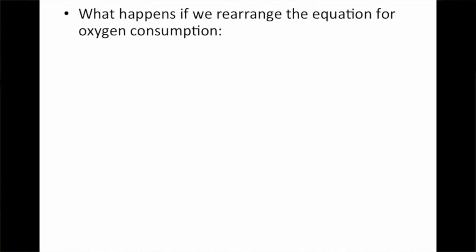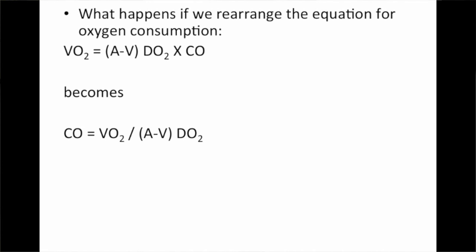That is the answer to the question asked of me as a fellow — 250 mL per minute is how low you can safely turn the flows down on the oxygen component of the anesthesia machine. But there's more: if you rearrange that equation and solve for cardiac output, you get cardiac output equals oxygen consumption divided by the AVDO2. That equation has a name — it's the Fick equation — and we've derived it from first principles.